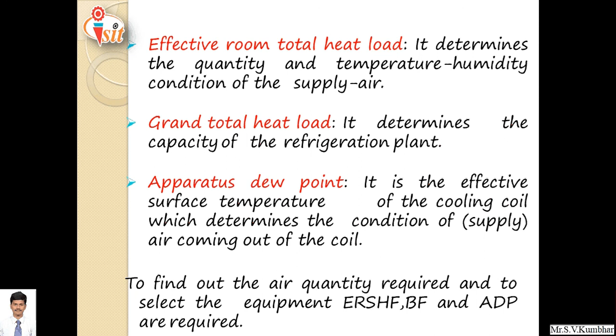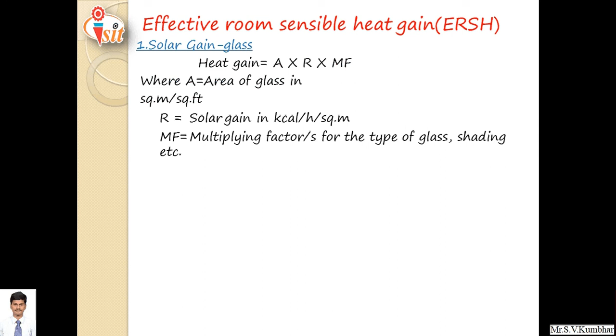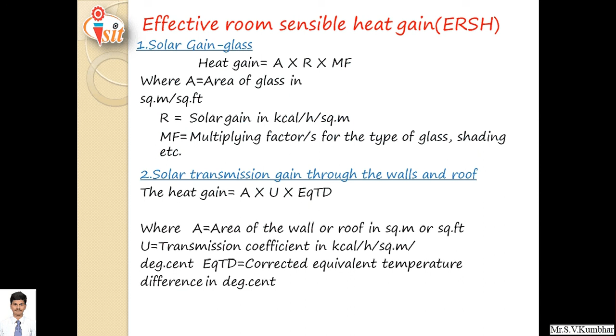Effective room sensible heat gain is calculated as follows. Solar gain through glass: heat gain is equal to A into R into MF, where A is the area of glass in square meter or square feet, R is the solar gain in kilocalorie per hour per square meter, and MF is the multiplying factor for the type of glass, shading, etc. Solar transmission gain through the wall and roof is generally calculated by U, the transmission coefficient, multiplied by area, multiplied by EQTD, where EQTD is the corrected equivalent temperature difference in degrees centigrade.